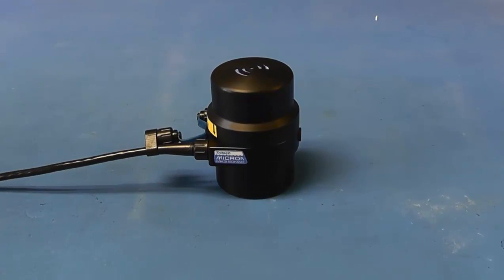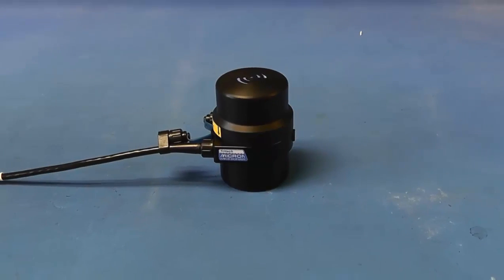The Tritech Micron connector is not wet-mateable and unused connector sockets are to be sealed against water ingress prior to subsea operations.